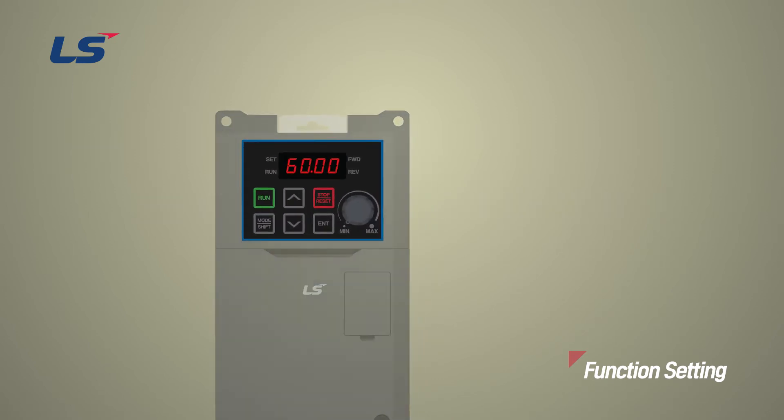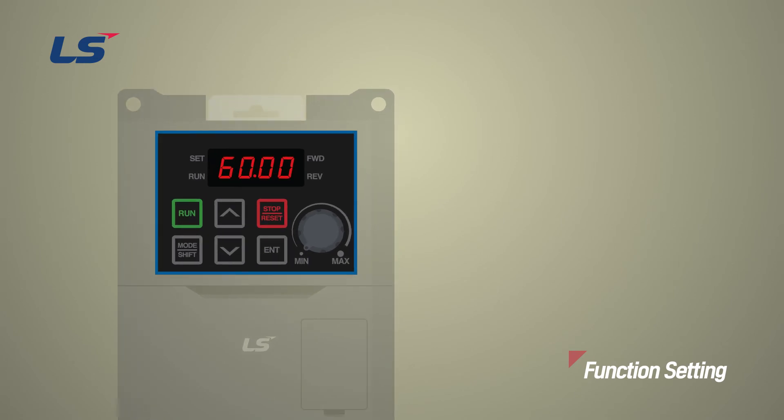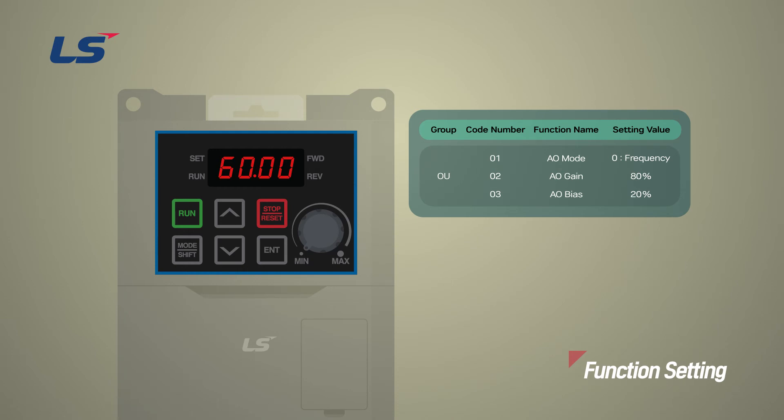Next, we will learn how to use the keypad to monitor the frequency through the output of 2 to 10 volts. In this video, we will set the output to 2 volts at 0 hertz and 10 volts at 60 hertz.